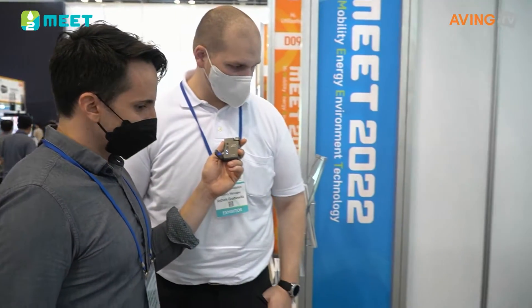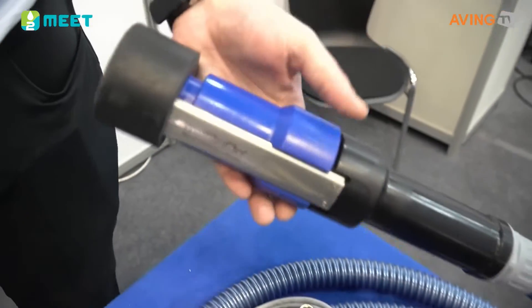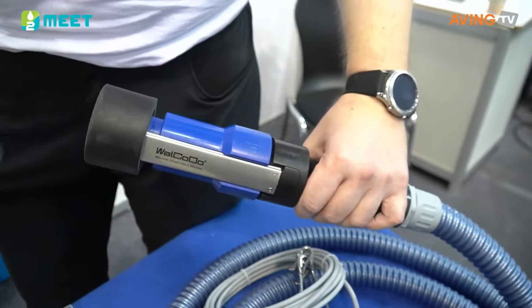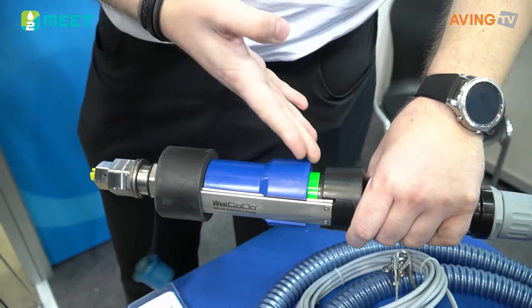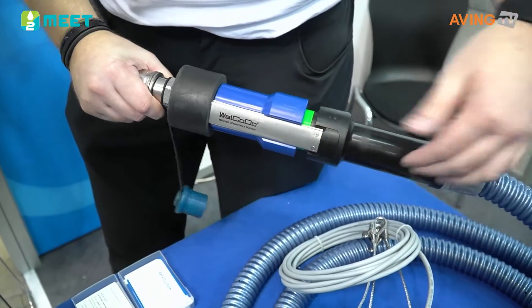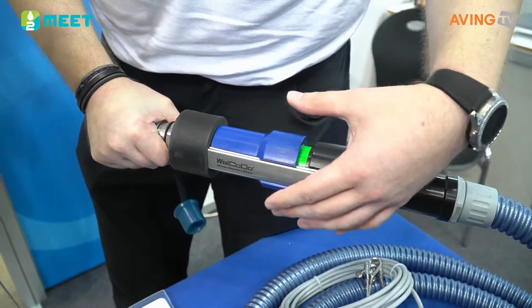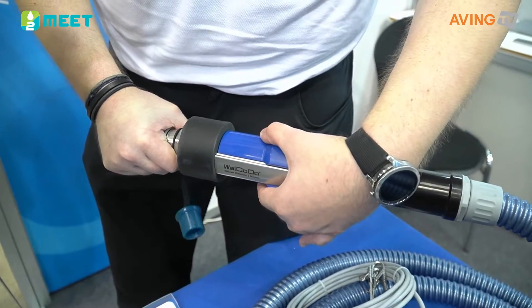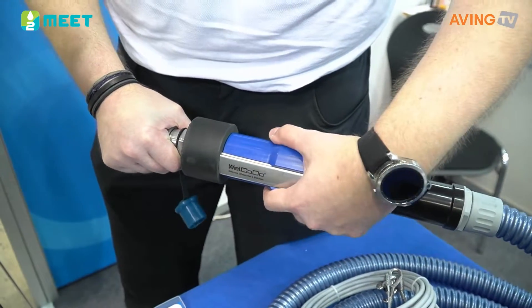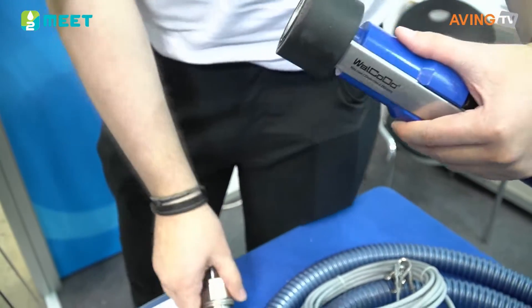This is a high pressure refueling system from Walter Precision. Here you can see the high pressure refueling nozzle for cars. It connects directly with the car — this is a receptacle for 700 bar. It's pretty easy to connect; you can see it's car coupled with a green indication showing coupling status. During refueling, a pressure active locking device prevents removing the nozzle from the receptacle. Once depressurized, you can remove it by pulling the blue sleeve and put it back in the parking station.